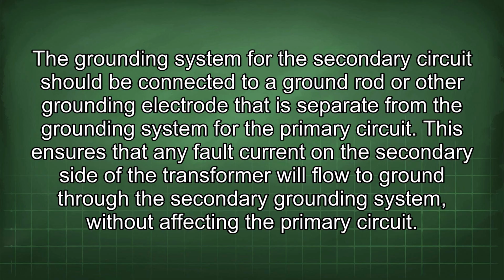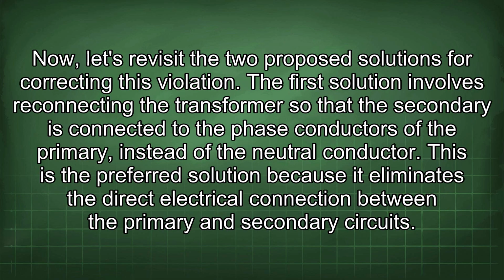This ensures that any fault current on the secondary side of the transformer will flow to ground through the secondary grounding system without affecting the primary circuit. Now, let's revisit the two proposed solutions for correcting this violation. The first solution involves reconnecting the transformer so that the secondary is connected to the phase conductors of the primary instead of the neutral conductor. This is the preferred solution because it eliminates the direct electrical connection between the primary and secondary circuits.